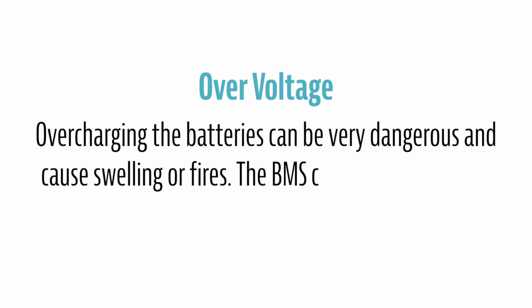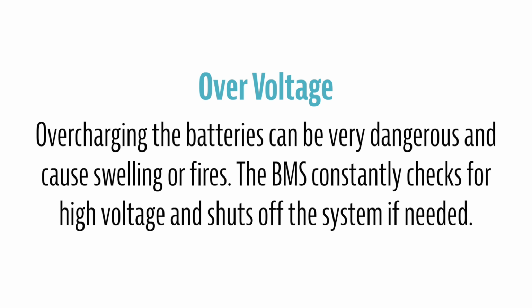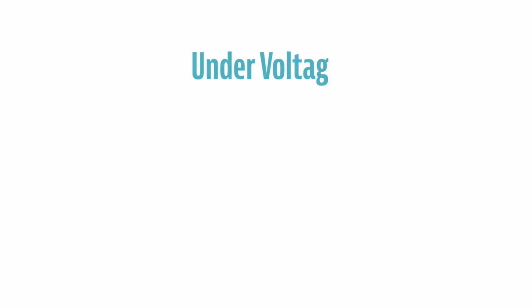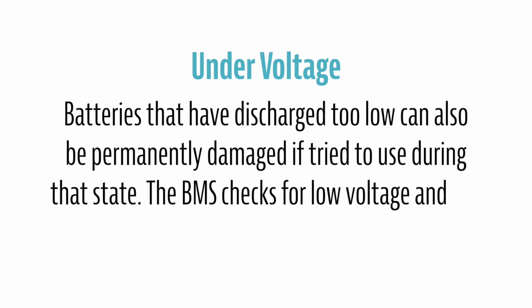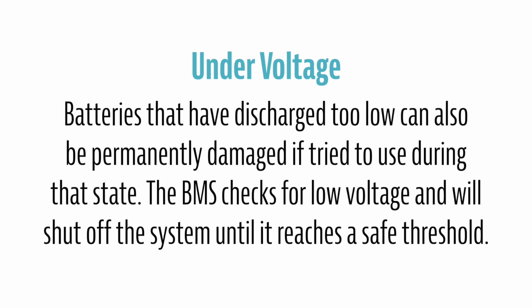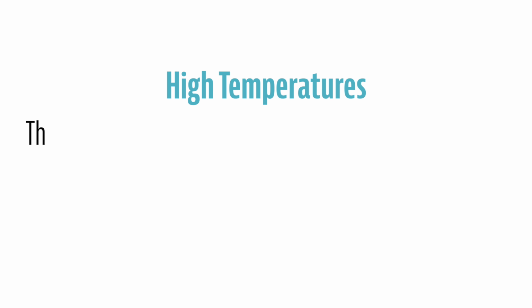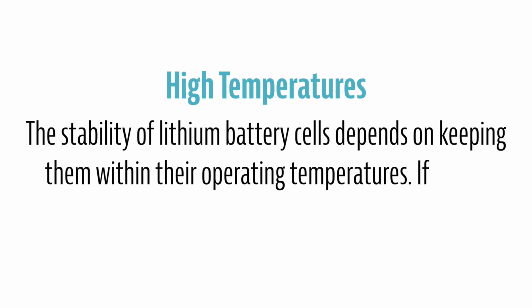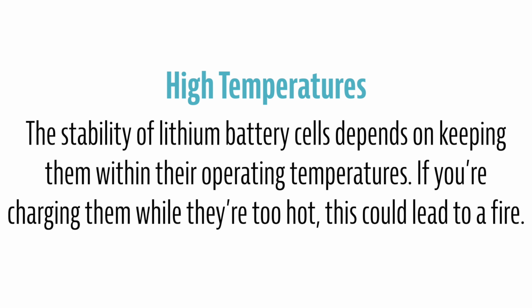Overvoltage. Overcharging the batteries can be very dangerous and cause swelling or fires. The BMS constantly checks for high voltage and shuts off the system if needed. Undervoltage. Batteries that have discharged too low can also be permanently damaged if you try to use them in that state. The BMS checks for low voltage and will shut off the system until it reaches a safe threshold. High temperatures. The stability of lithium battery cells depends on keeping them within their operating temperatures. If you're charging them while they're too hot, this could lead to a fire.